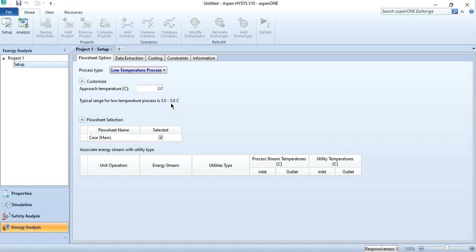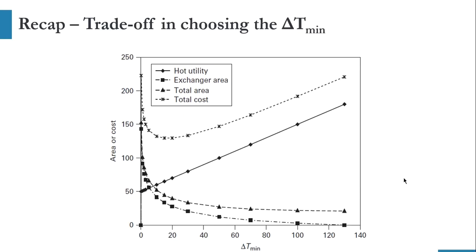When you are at ambient or near ambient conditions — above ambient — the range is between 10 to 20 degrees centigrade. When you go further above ambient, like 100 or 200 degrees centigrade, the range goes to 20 plus. And as you can see for hydrotreater systems where high temperatures are employed, this range can even go to 30 to 40 degrees centigrade. So this value of delta T minimum is dependent on the process. The factors we discussed — utilities, exchanger area, total area, and total cost — will also be included, and for simpler plants the 10 to 20 degree range applies, while for low temperature processes the configurations will change.